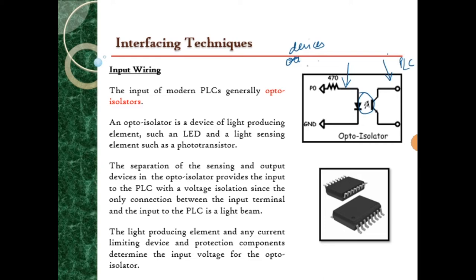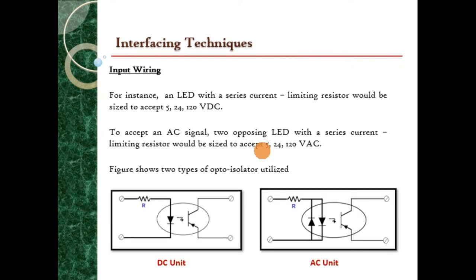The use of an opto-isolator in the PLC is to prevent high voltage from affecting the system. That's why they use the opto-isolator to connect these two isolated circuits, to avoid any high voltage or high current interference affecting either of the systems. There are two types of opto-isolator. The first is the opto-isolator for DC unit PLCs, and the second is the opto-isolator for AC unit PLCs.